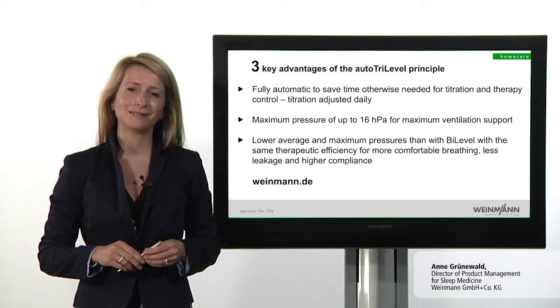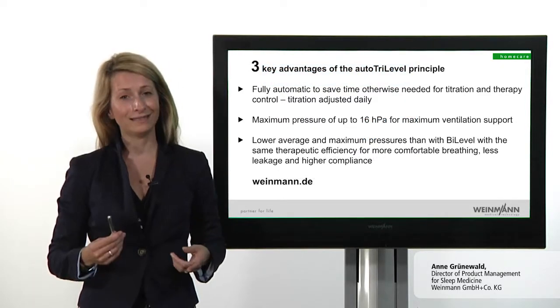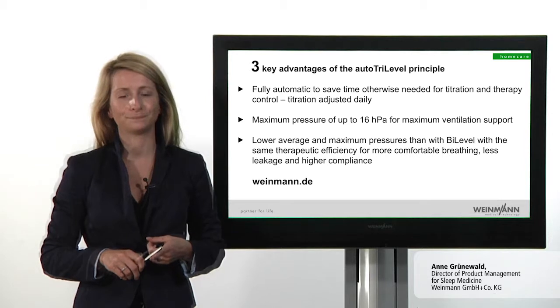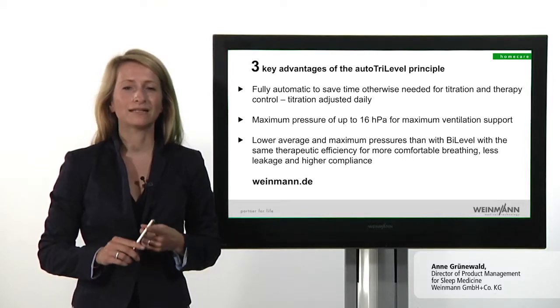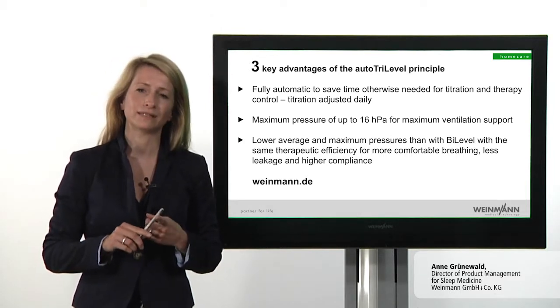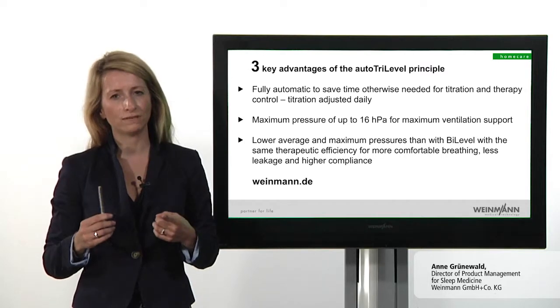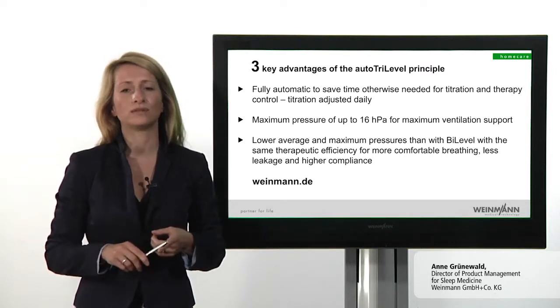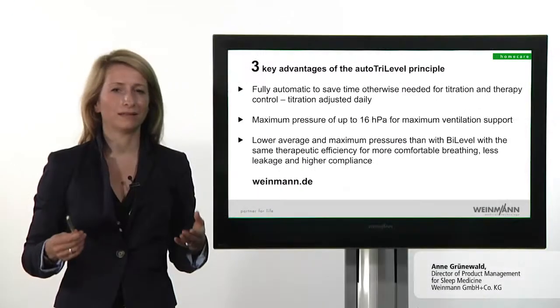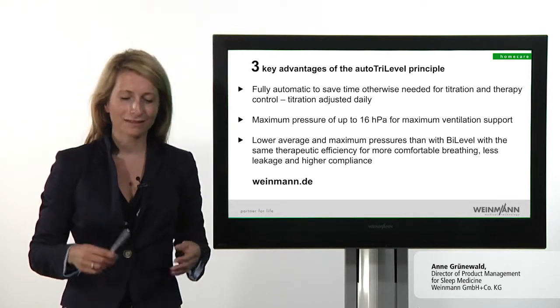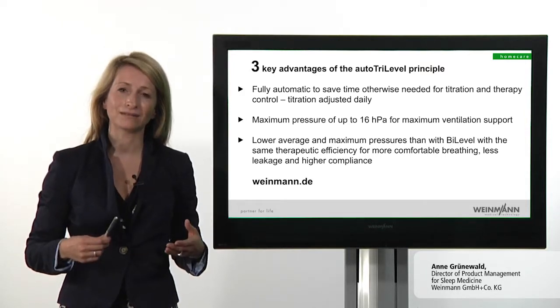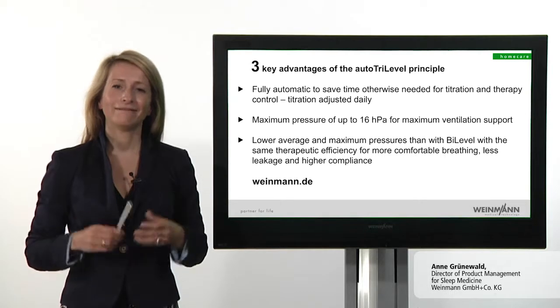The special attractions of the auto-tri-level principle can be summed up in the following three points. Firstly, it's fully automatic and, as such, offers the very best support to medical staff in their daily routine. Both IPAP and EPAP are automatically adjusted to meet the individual patient's needs within the pressure levels required by the particular therapy. They also efficiently treat both obstructive and central events and phases of hypoventilation. The advantages for you are that you save time otherwise spent adjusting devices and monitoring therapies. The patient receives optimum therapy at all times, as though titration were re-performed every day, even for patients with complex, constantly fluctuating breathing patterns.